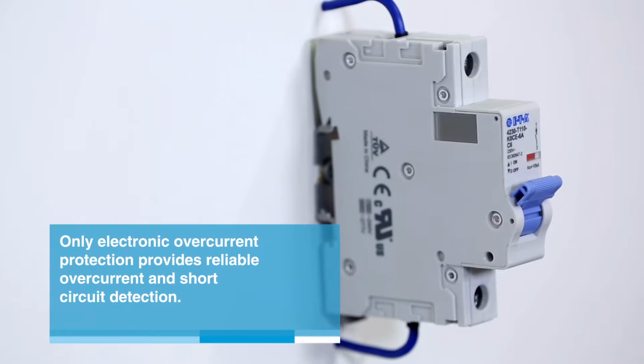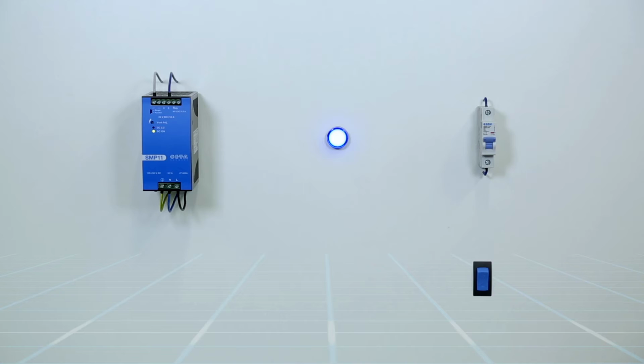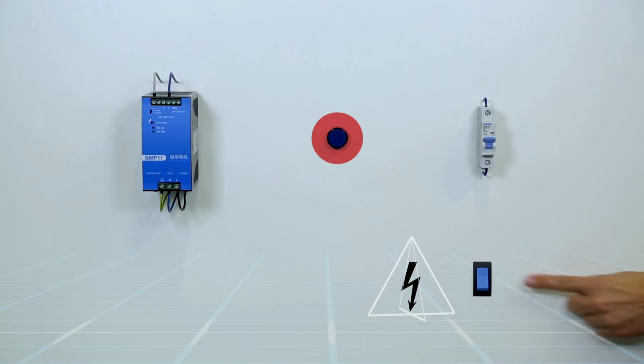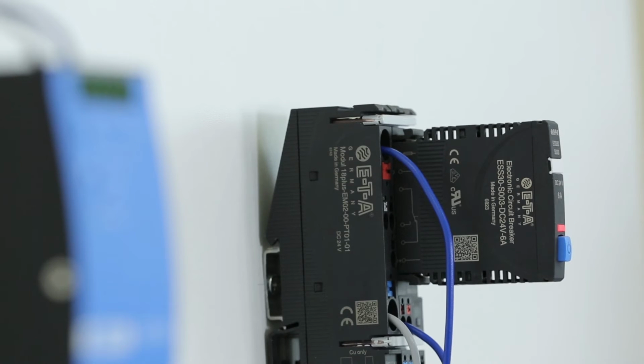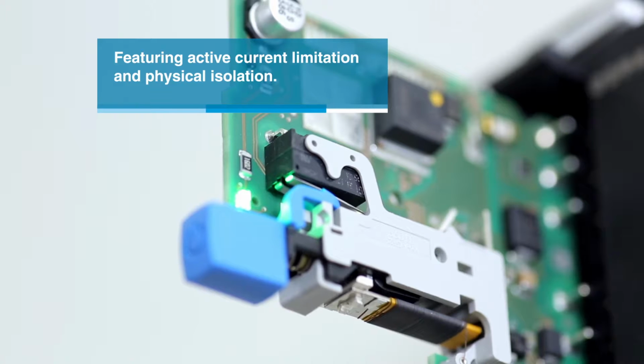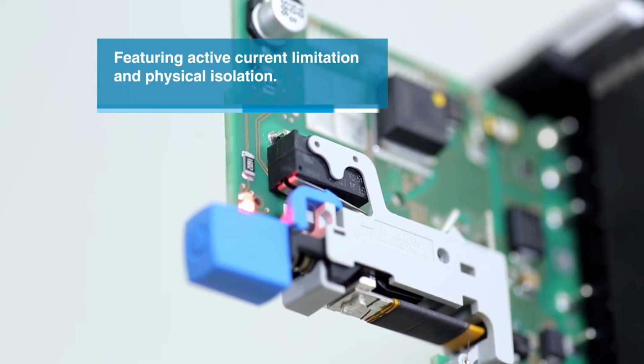In the event of a failure, a switch mode power supply will not provide enough current to make conventional protective elements trip. Long cables and the resulting resistance values are further impediments. The electronic circuit breaker combines current limitation and electronic overcurrent protection with VDE and UL-compliant physical isolation.